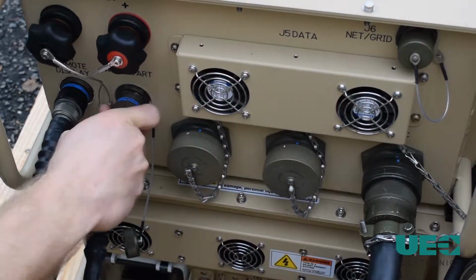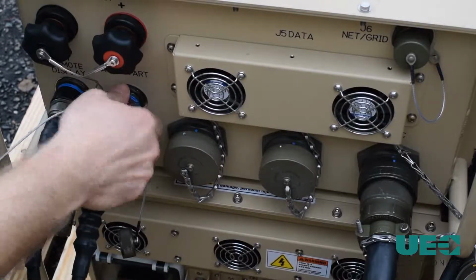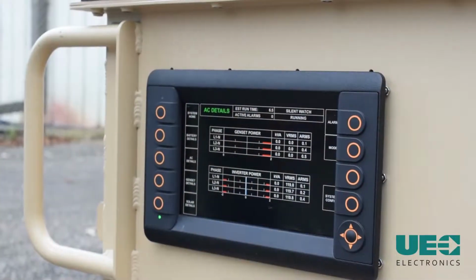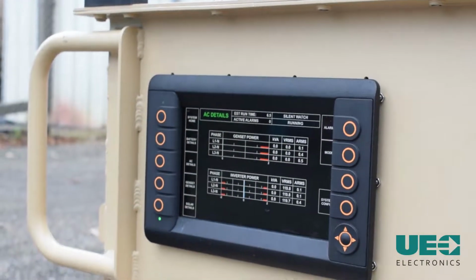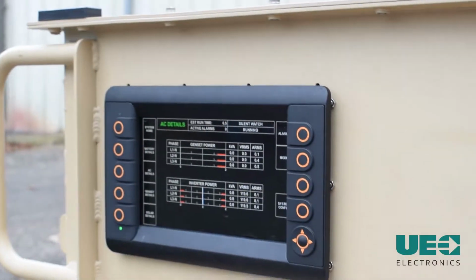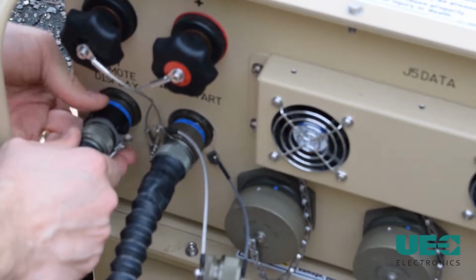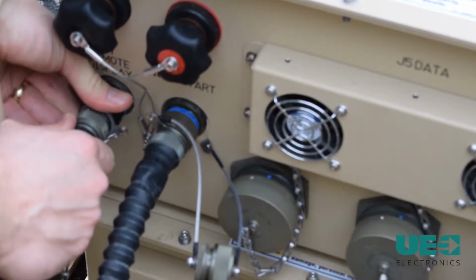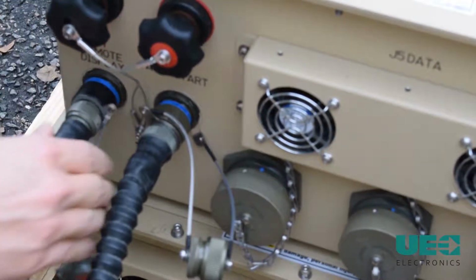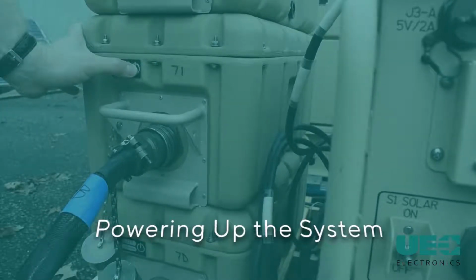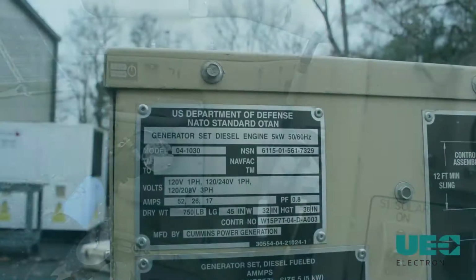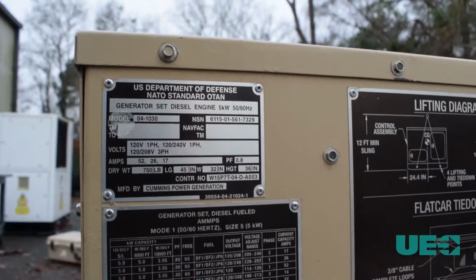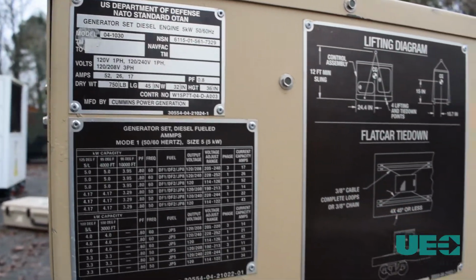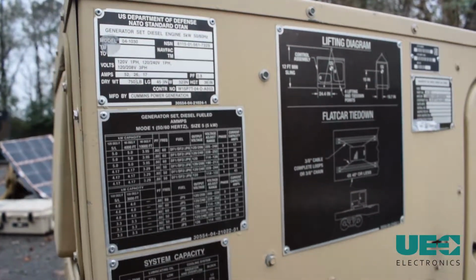Using the auto start cable, connect the DC PDU to the generator. The system can be monitored with the HMI that is integrated into the DC PDU. If monitoring the system remotely, connect the remote HMI to the DC PDU. After everything is connected, you are now ready for powering up the system. Verify that the generator is in proper working order and that all fluid levels are acceptable.